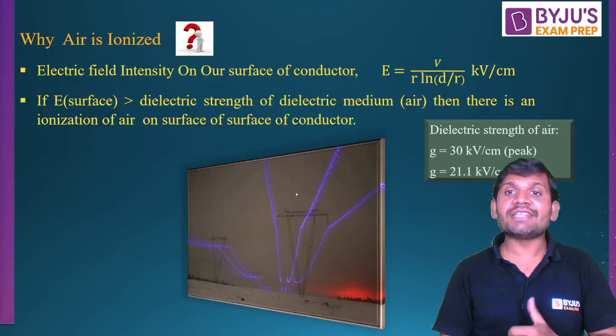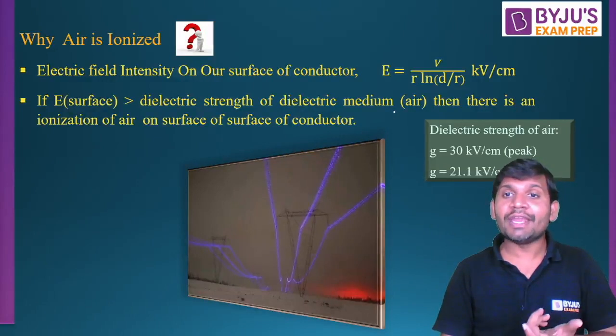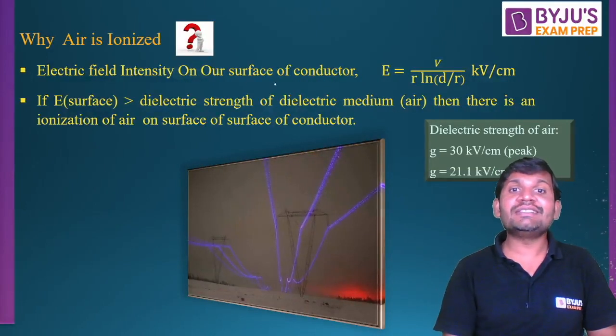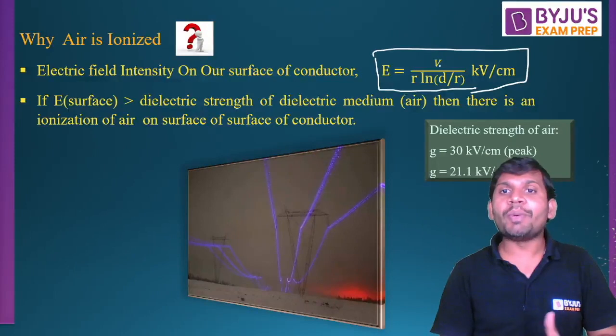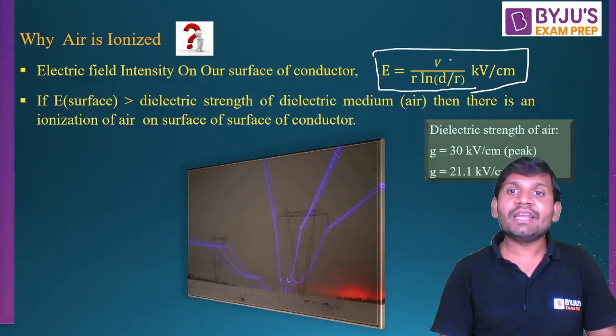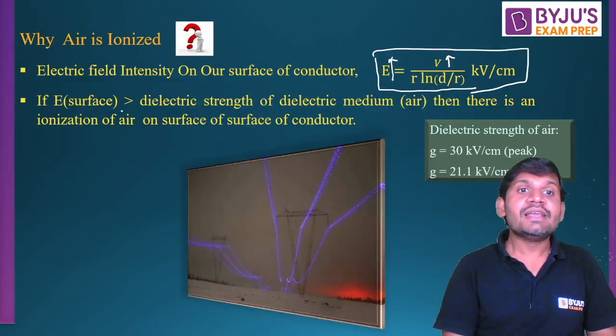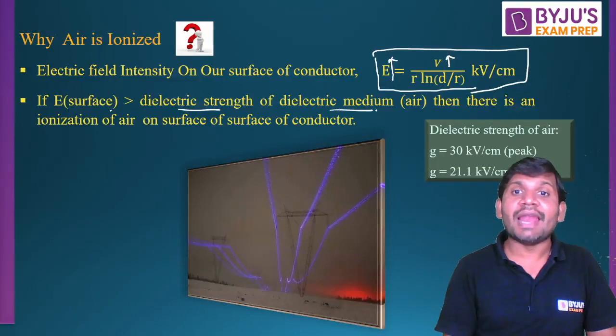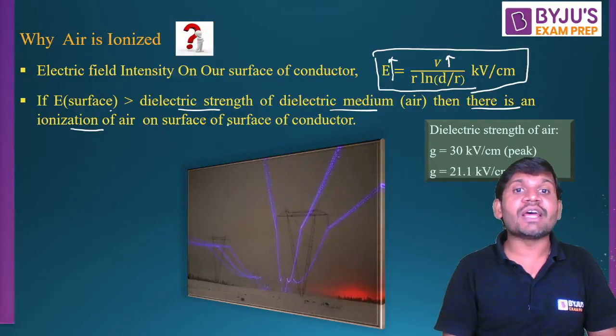Why does ionization of air take place around the conductor? If the lines are operating at high voltages greater than 220 kV, the corona effect is appreciable; for less than 220 kV, it is not appreciable. The electric field intensity on the surface of the conductor is given by a formula where V is the operating voltage and E is the electric field intensity. When the operating voltage increases — that is V greater than 220 kV — the electric field intensity also increases. When the electric field intensity on the surface of the conductor exceeds the dielectric strength of the dielectric medium, which may be air, then there is ionization of air on the surface of the conductor.